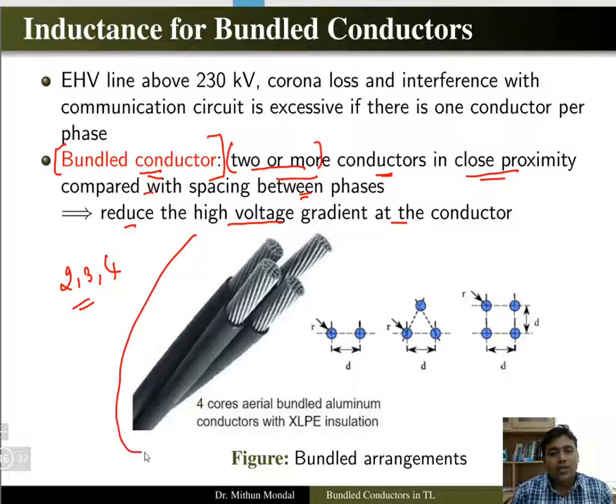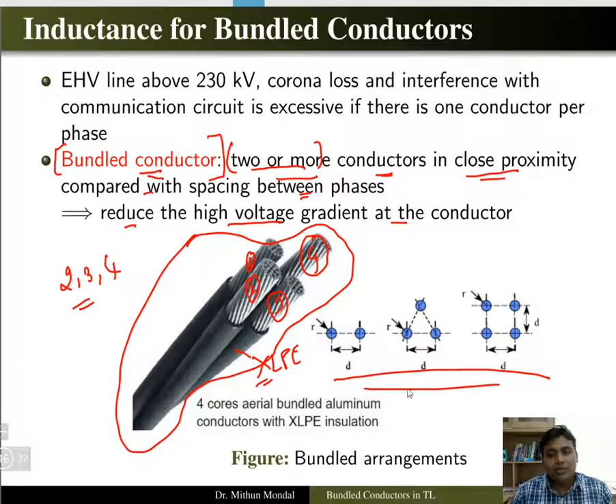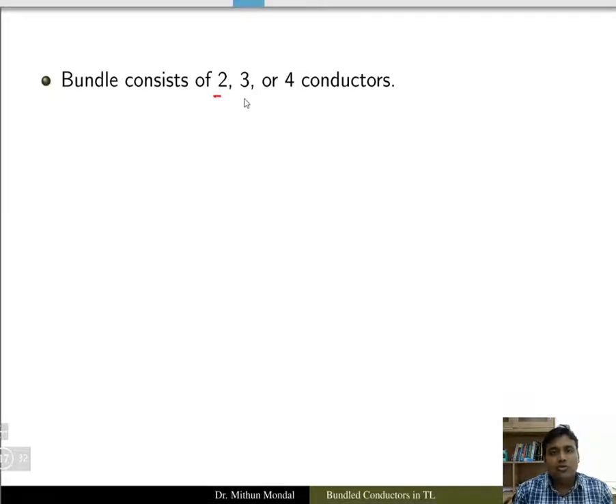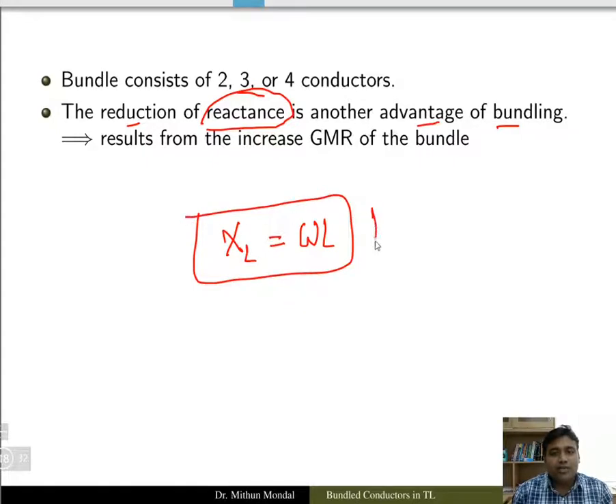Here you can see one bundle arrangement with four cores — core number one, two, three, and four — with XLPE insulation. Configurations can have two, three, or four conductors in a group, where small d is the distance between conductors and r is the radius of the conductor. Bundle conductors with two, three, or four conductors in a group will reduce the reactance of the transmission line, which is a big advantage of bundling, since XL = ωL.